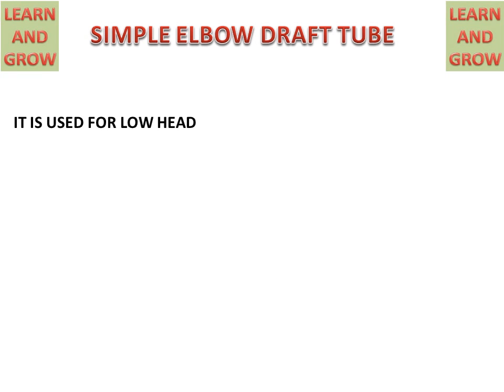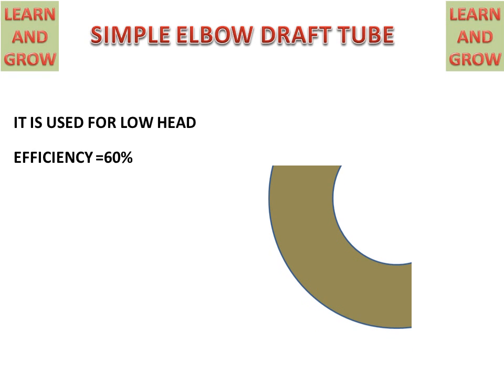Simple elbow draft tube. This is used for low head and its efficiency is about 60%. It looks like a simple elbow with no change in the area of the elbow. The inlet will be from the upper side and water will go out from the lower side. This is the simple elbow draft tube.